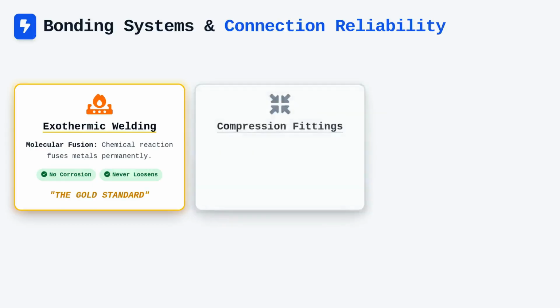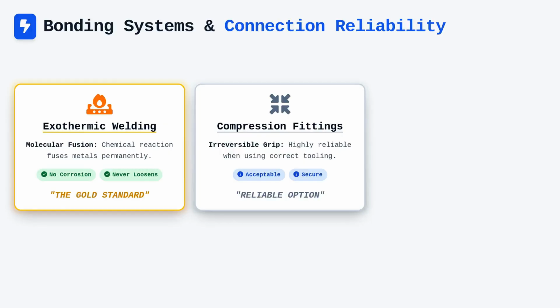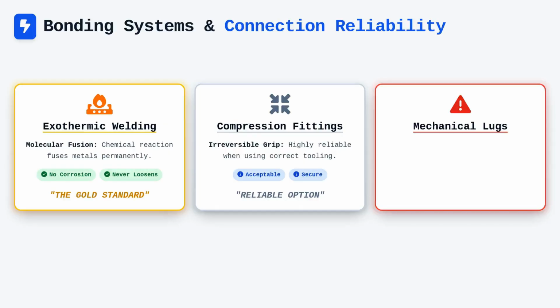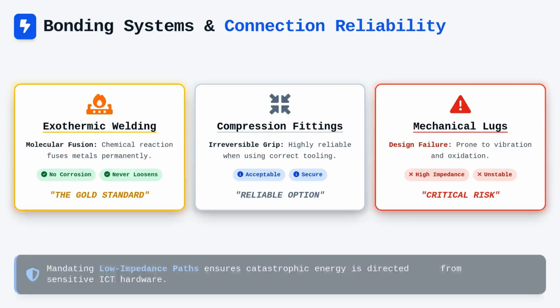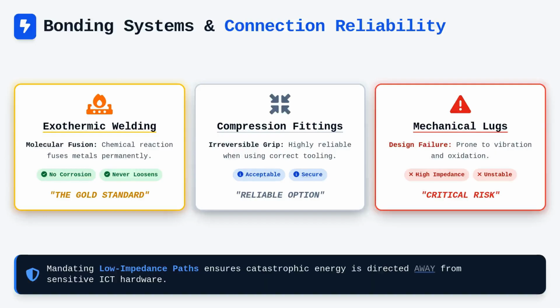While irreversible compression fittings are also acceptable and highly reliable when installed with the correct tooling, they do not offer the same structural integrity as a molecularly fused bond. A common design failure is relying on mechanical lugs that can vibrate loose or oxidize, leading to a high-impedance connection that might fail exactly when you need it most. By mandating low-impedance paths that are structurally sound, we ensure that catastrophic electrical energy is directed away from our sensitive ICT hardware rather than through it.